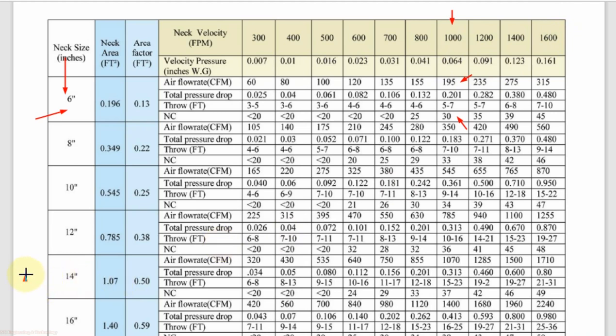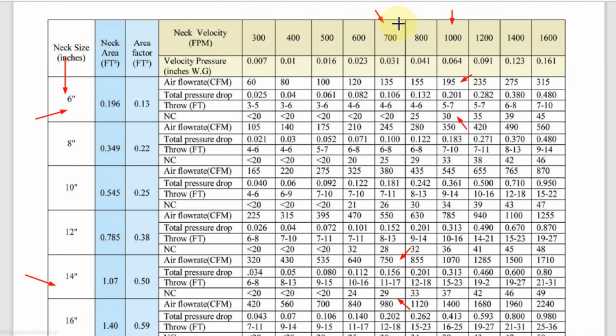Similarly, for 14-inch round ceiling diffuser, we check the NC level. Our maximum limit is 30. We see 29, then 33, so we select the 29 NC value. The corresponding CFM value is 750, and the corresponding neck velocity required is 700 FPM. If we have 700 FPM neck velocity in our duct, we can select a 14-inch round ceiling diffuser for a maximum CFM of 750.